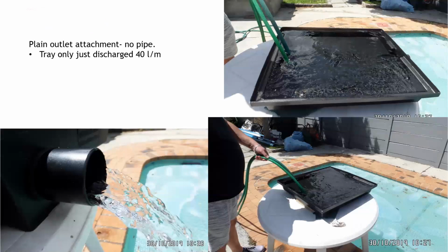So here's just a plain outlet, without even a pipe attached to it. Now, 40 liters coming in to the tray. Have a look at the level of that water. It is almost overflowing. It is not a happy tray. It's handling it, but it is almost overflowing. It has no outlet pipe, nothing, it's just the fitting. By the way, there's another picture of that fitting not even in the tray, and it's doing exactly the same thing. So just the tray with its outlet, it's doing exactly the same thing.